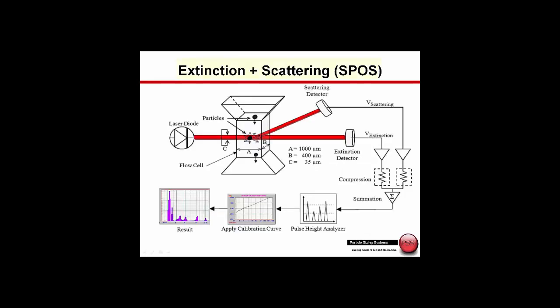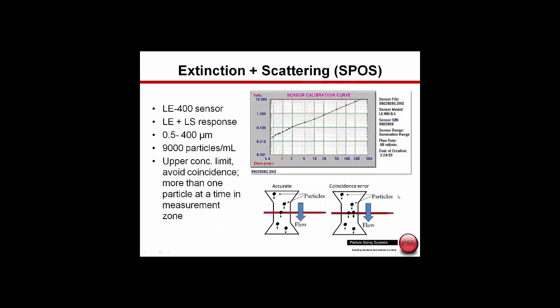In order to improve the dynamic range, Particle Sizing Systems has created the single particle optical sizing sensor, which has both an extinction sensor plus a scattering sensor. We're actually going to use a detector to look at this additional light scattering, which we could think of as a positive pulse. We take these two pulses, the extinction and the scattering, combine them, and then take this combined pulse and use it to convert to the size distribution.